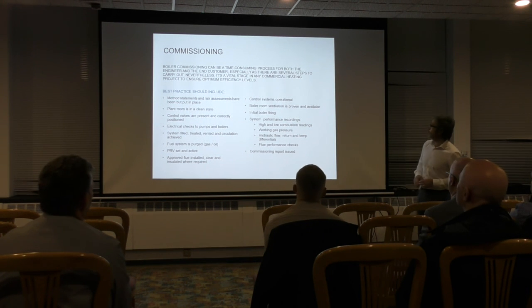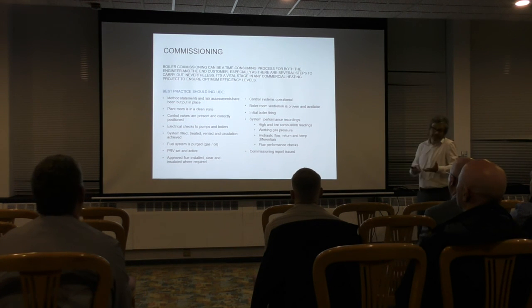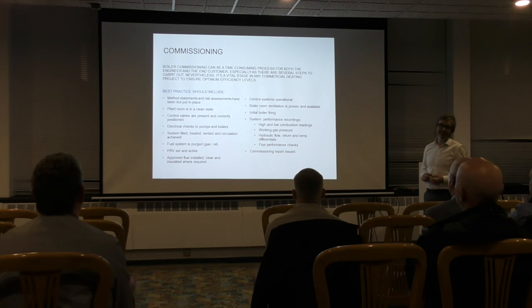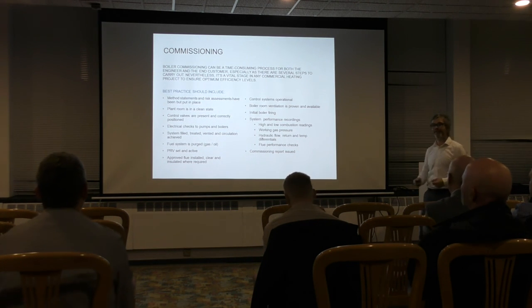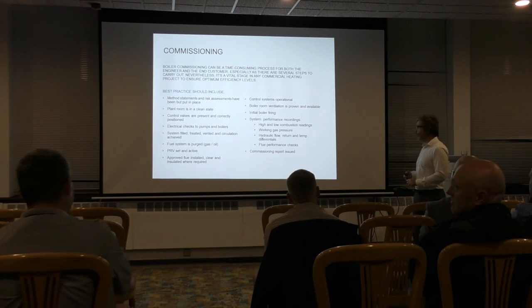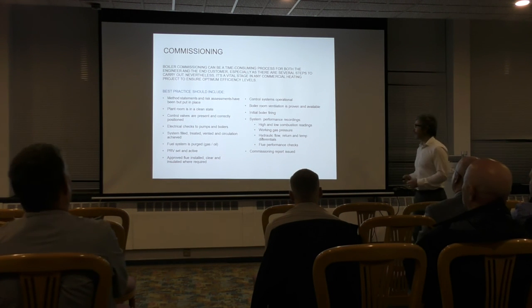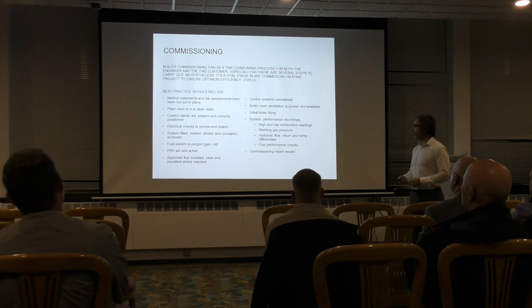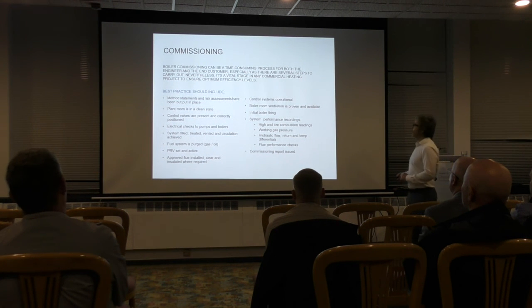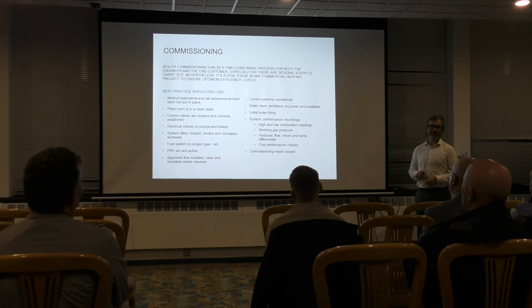Make sure the control valves are present and correctly positioned. Make sure there's electric to everything. Make sure the system's filled, so we've got water in the system. All sounds obvious, but these are all points that we have come up against, and we've been expected to commission boilers when we have no water in the system. Make sure the fuel system's purged, PRV set and active. Make sure we've got flue installed as well. Control systems are operational, the boiler room ventilation is proven and available, and the boilers have been initially fired.